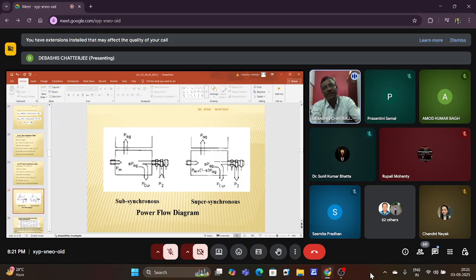So this is the air gap power, which is actually the stator power. Let us say you neglect stator losses, so this is stator power being fed. Now when rotor power is inserted, right, rotor power is into the system, so it can generate below synchronous speed where we are feeding the stator power. This is the mechanical input power, this is the rotor copper loss. So net power available is actually PAG minus P2, neglecting stator losses, because P2 we are feeding and PAG we are getting. And naturally PAG is more than P2 because mechanical power is there. So if you take this as node, PM plus P2 is PAG, right? So this way you can think.